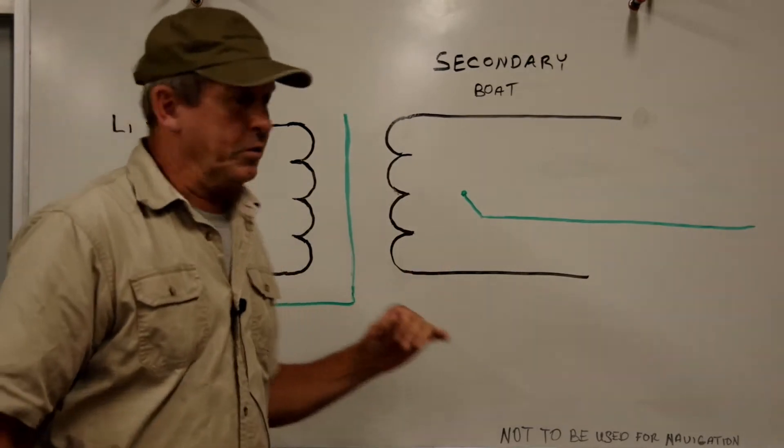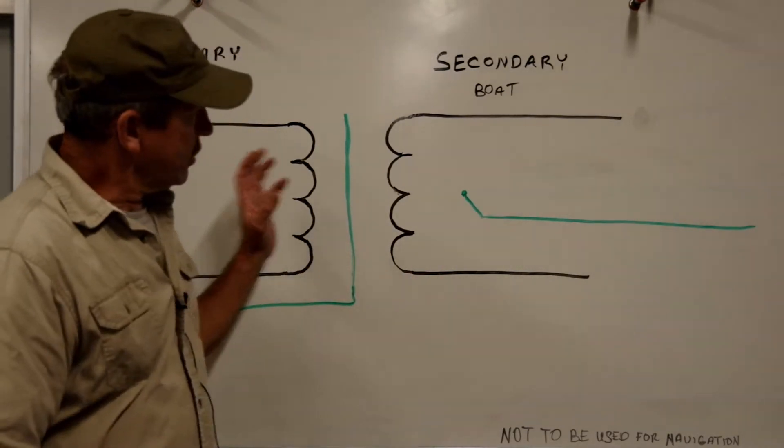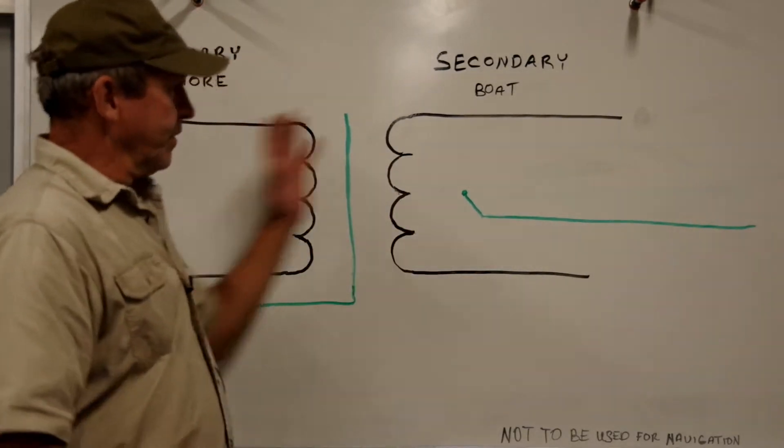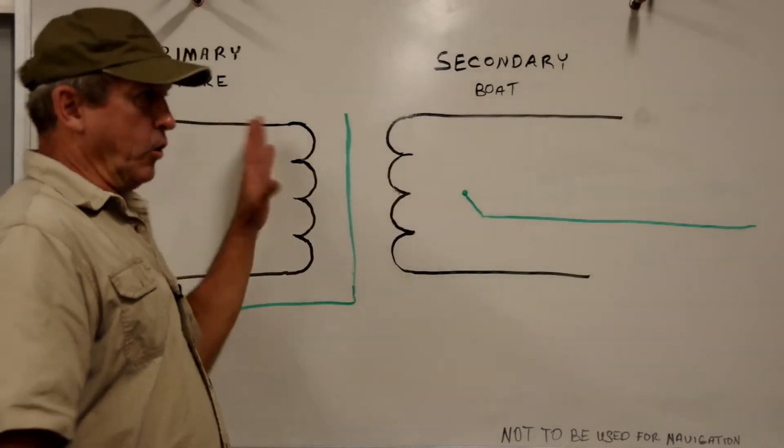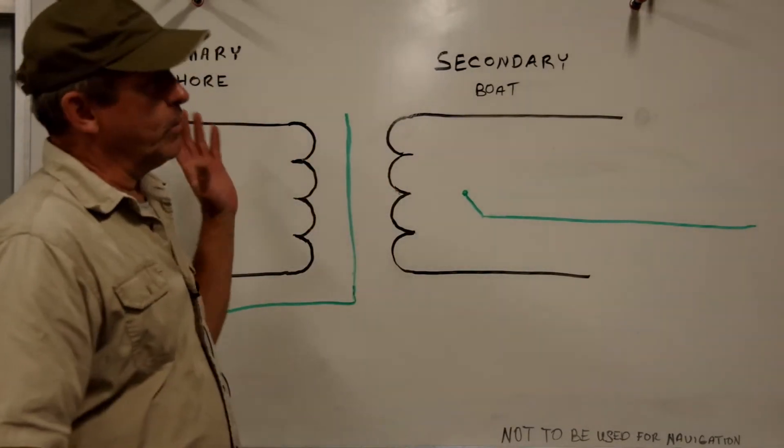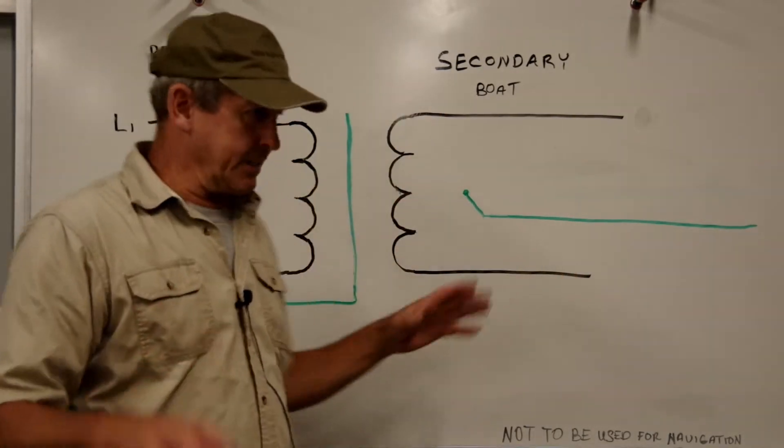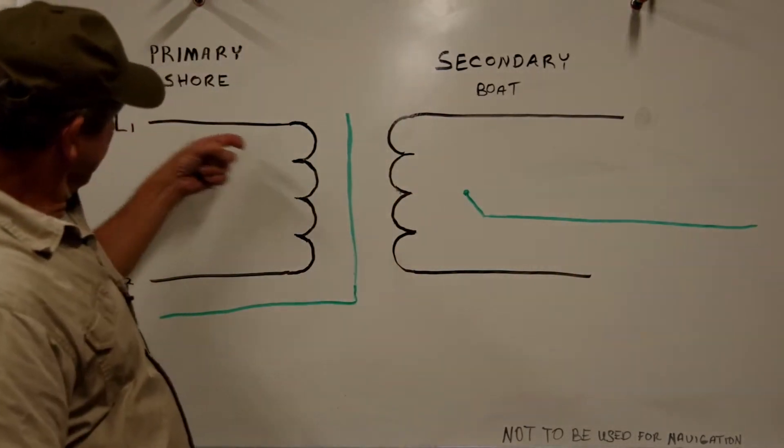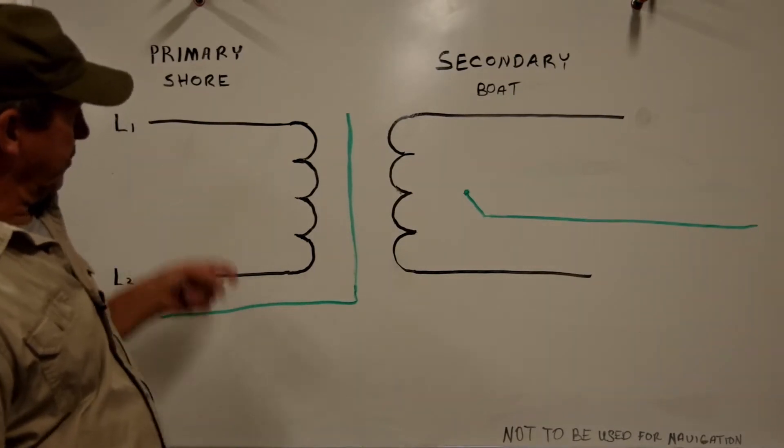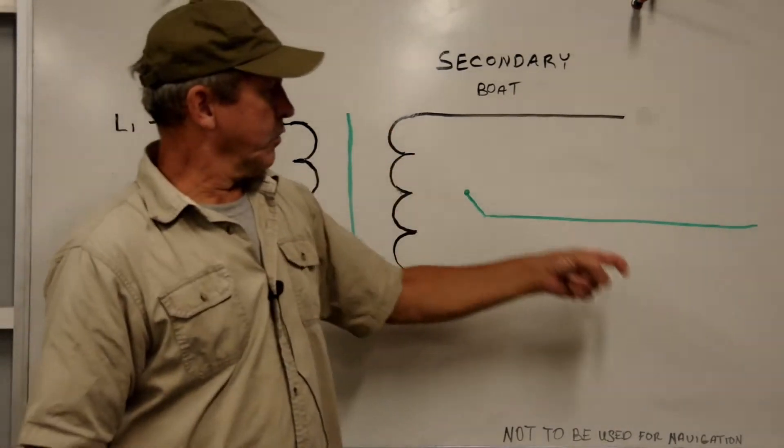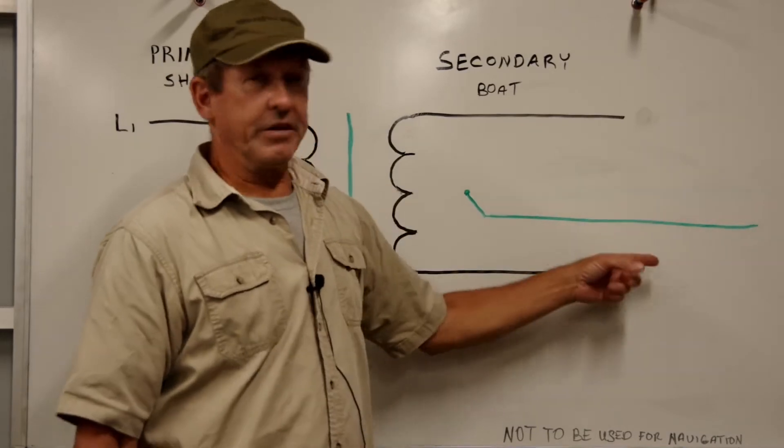Now the beauty of these things is we say isolation transformer—we've isolated our boat from the dock. There is no physical, mechanical, electrical connection between the boat and the dock, so we're isolated. We send 240 volts in on the primary, we get 240 volts out on the secondary.